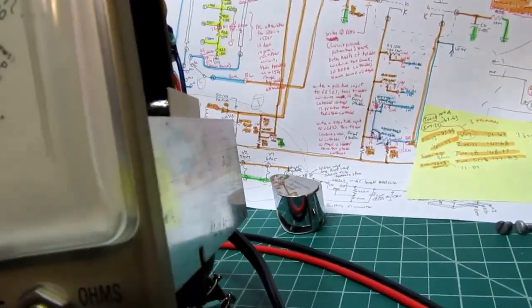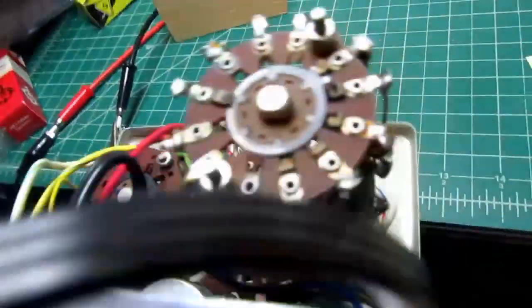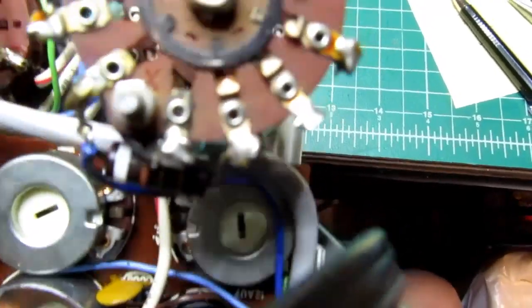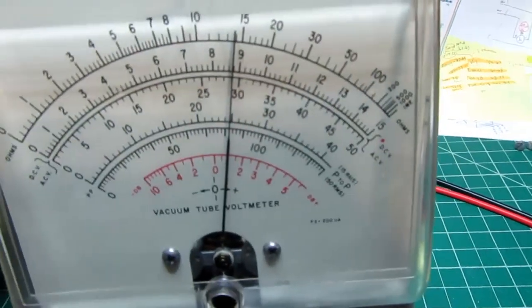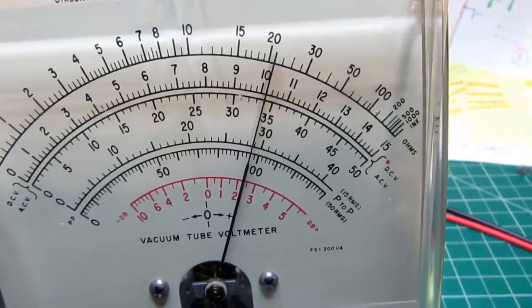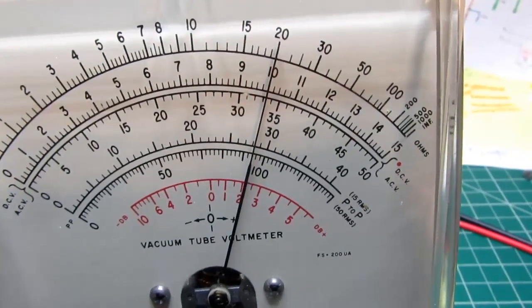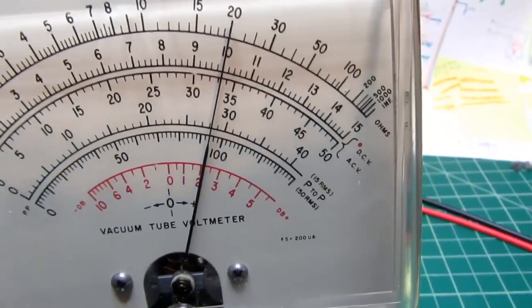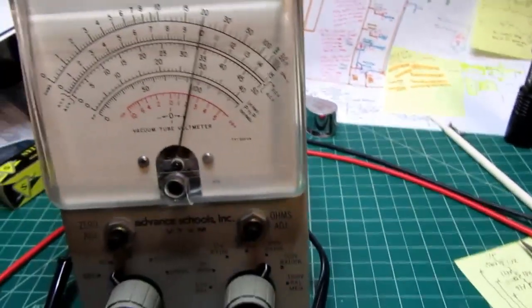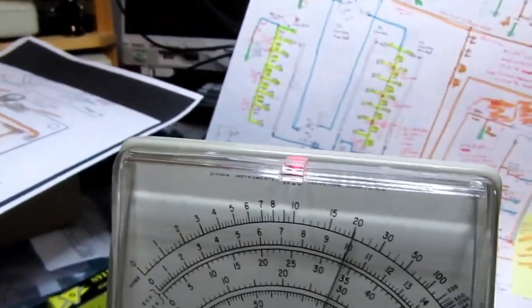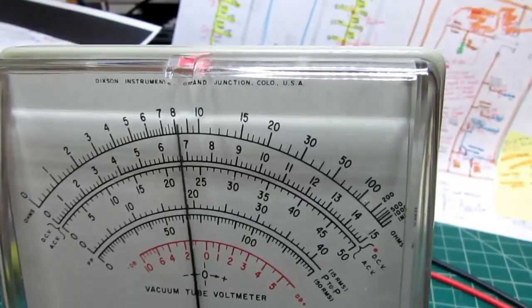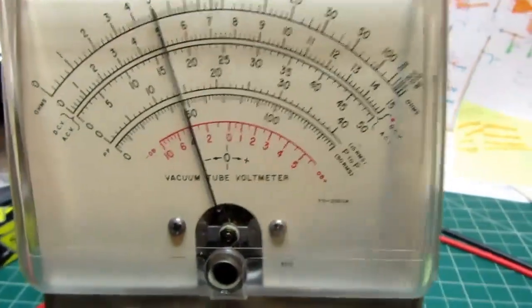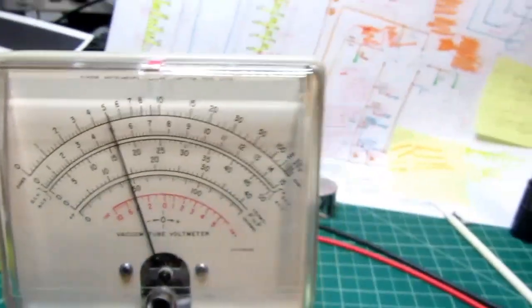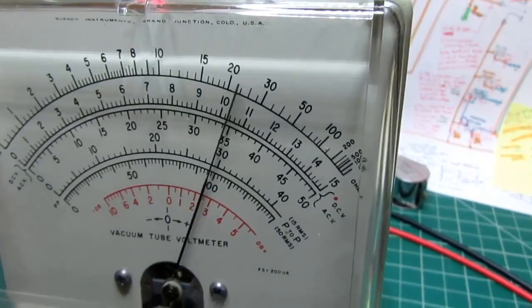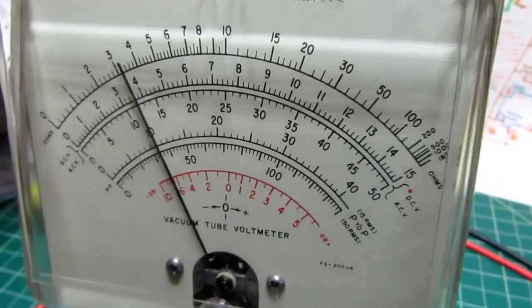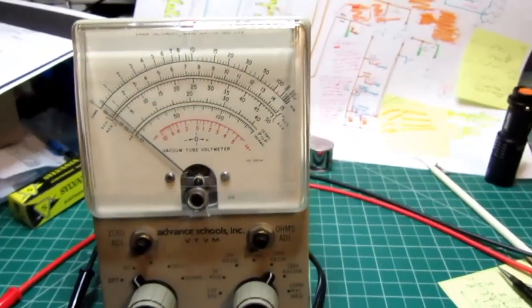So the AC cal pot is this one over on the right side of the circuit board. Alright, so it's right up to 100 now, so that's calibrated. And if I crank the variac down to about 50 volts, we should be getting 50 volts here. So that's working pretty well. That's all the calibration there is to do on these meters.